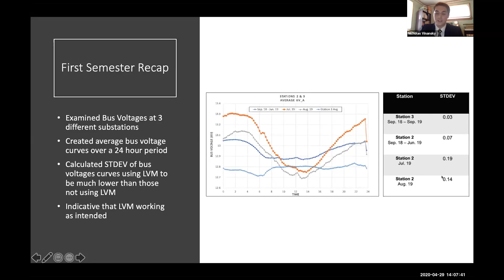As shown by the results on the right-hand side, Station 3, which operated under LVM for the whole year, had a standard deviation of 0.03 in the bus curve. Station 2, which operated for a portion of the year under LVM, had a standard deviation of 0.07, also very low. For the months of July and August, when Station 2 did not utilize LVM, it experienced much higher standard deviations.